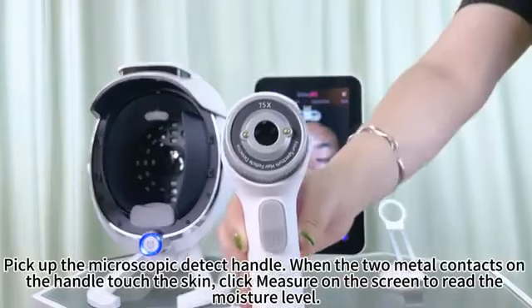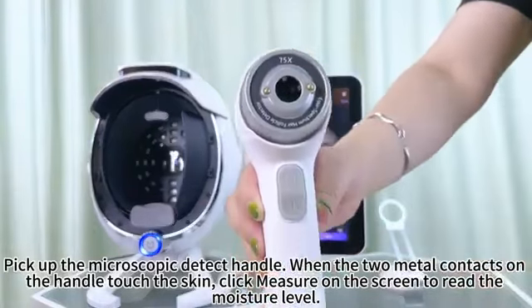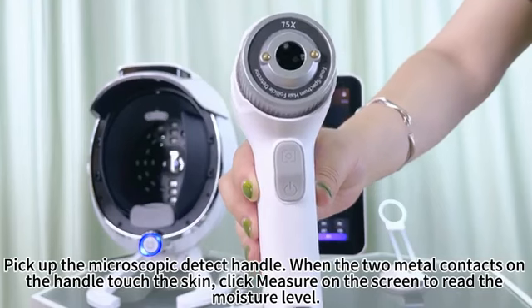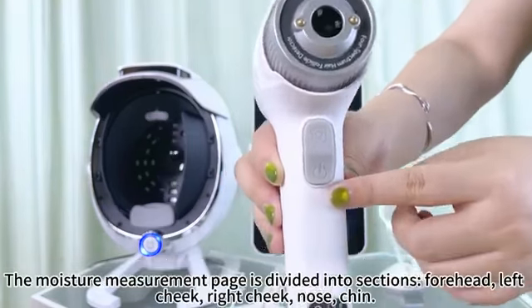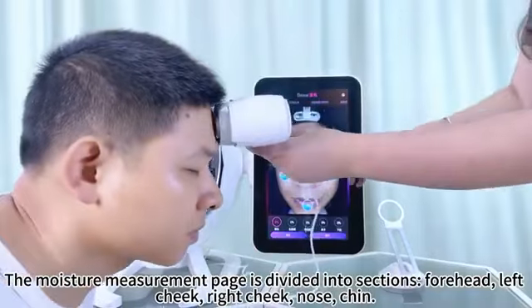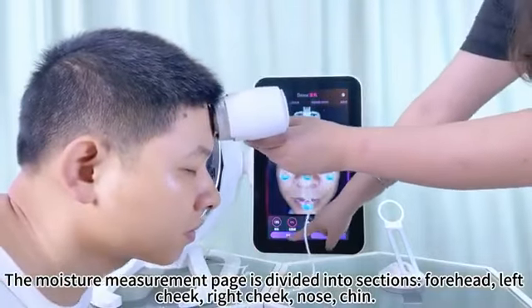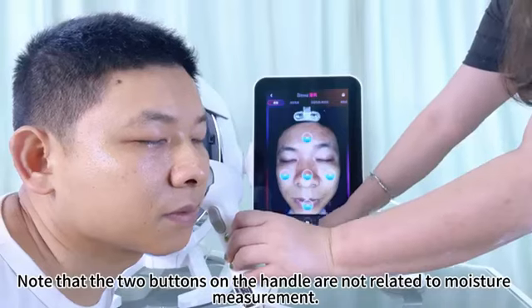Pick up the microscopic detect handle. When the two metal contacts on the handle touch the skin, click Measure on the screen to read the moisture level. The moisture measurement page is divided into sections: forehead, left cheek, right cheek, nose, chin. Note that the two buttons on the handle are not related to moisture measurement.